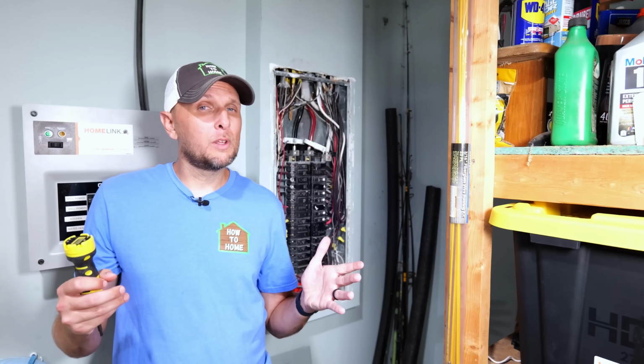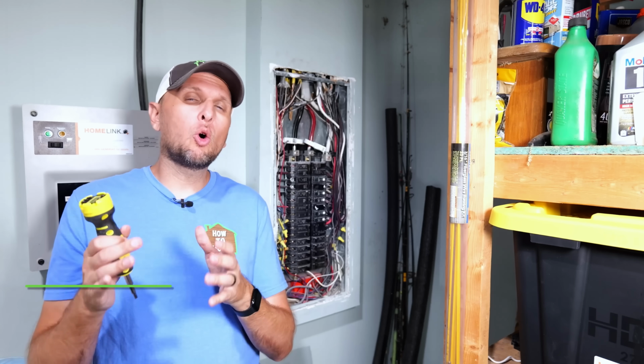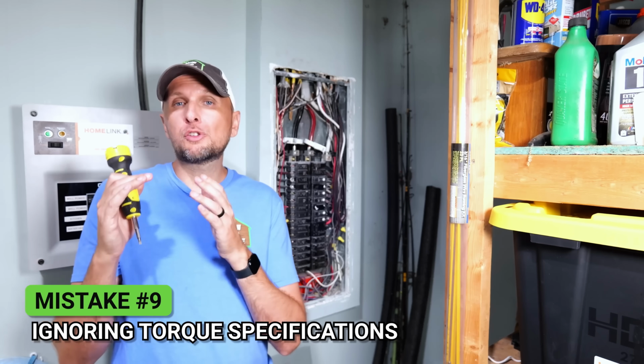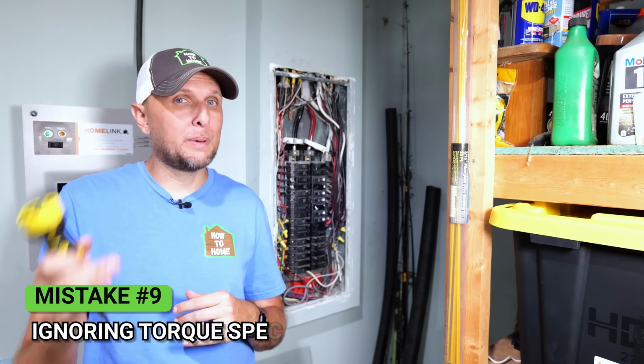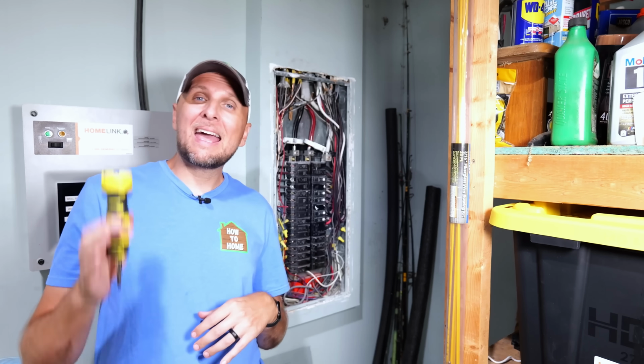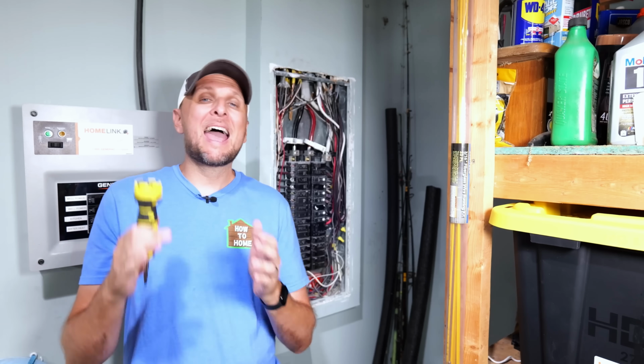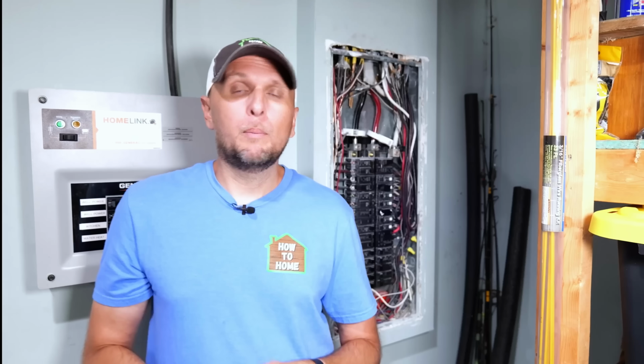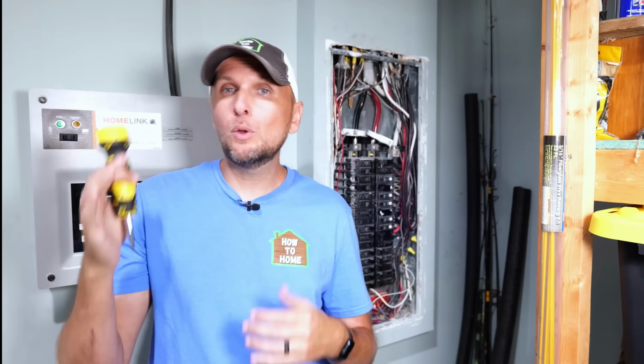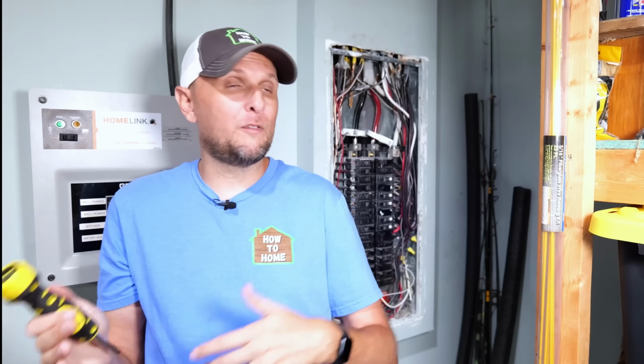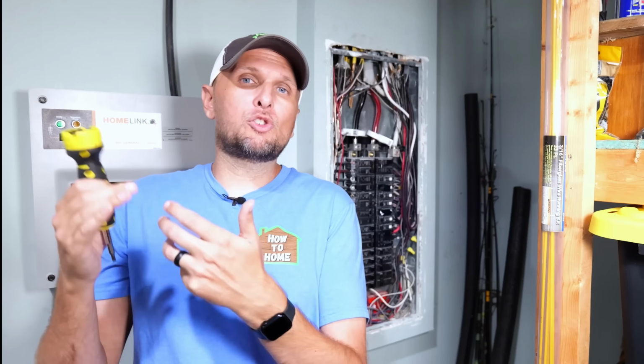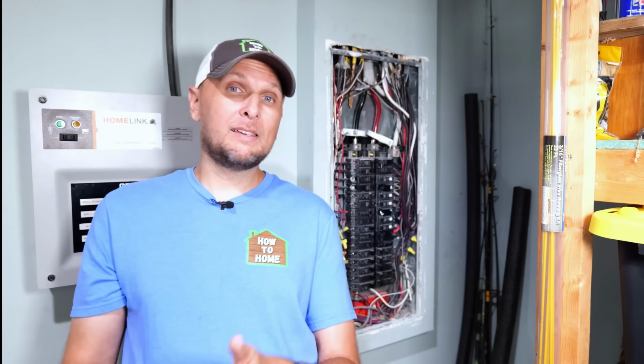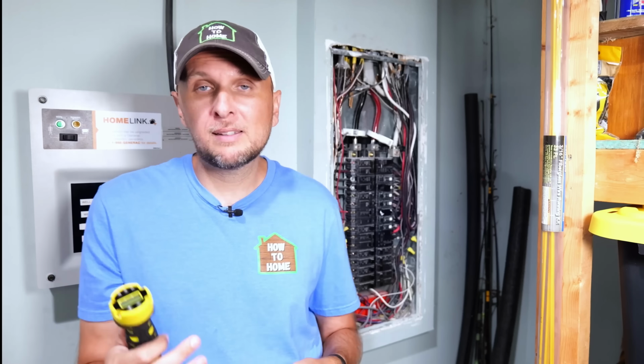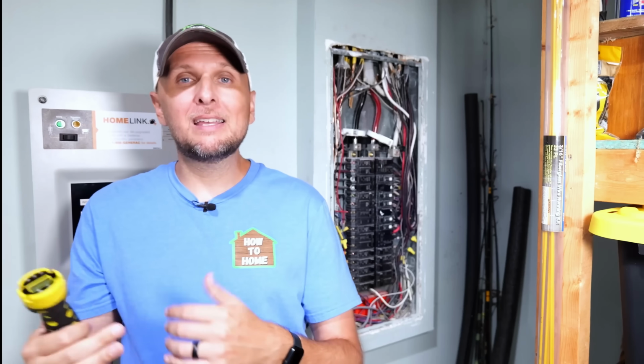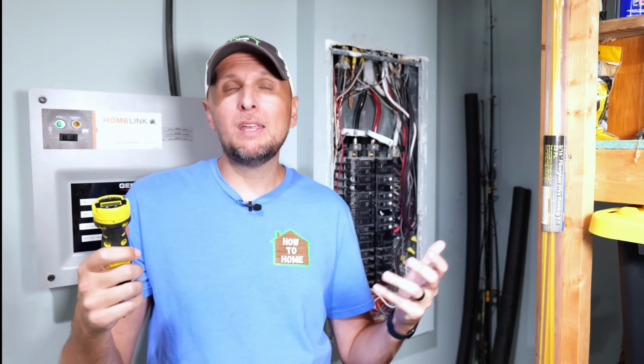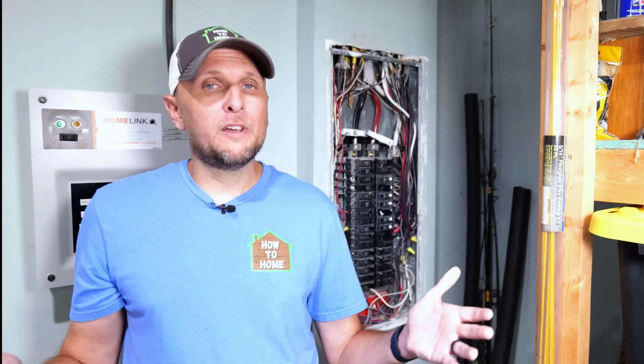This next big mistake comes down to ignoring the torque specification for the screws and lugs in your panel. A lot of people don't realize every connection in your panel has a specific torque setting. If you leave them too loose, you might get arcing; too tight, and you risk stripping the screw. I've personally seen loose lugs cause hot spots, which can quickly damage your breakers and even your wires.